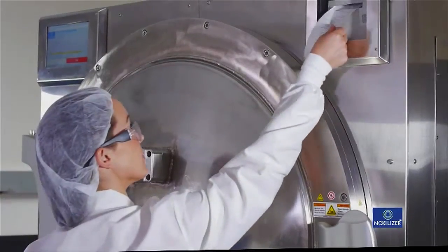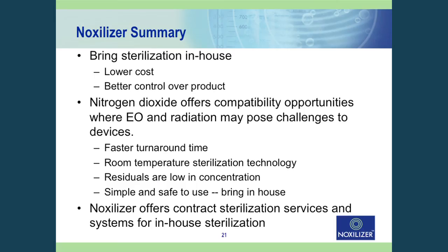Part of the UL safety testing and IEC testing completed for our CE mark includes the locking mechanism, interlocks, printers, and all parts of the sterilizer required by ISO regulations. The benefit of using nitrogen dioxide is a low-temperature sterilization process you can bring in-house that will serve most medical devices you package yourself. For contract sterilization, the Noxilizer system offers small batches and rapid turnaround, without days spent in aeration or preconditioning. The room temperature process is obviously advantageous for some materials, and the system is plugged into the wall, freestanding, pulls in room air, exhausts to the room, and is a complete sterilization system.